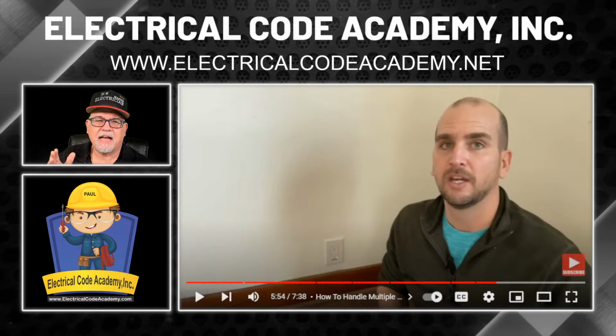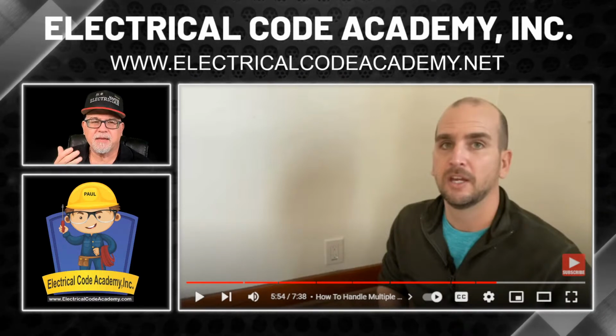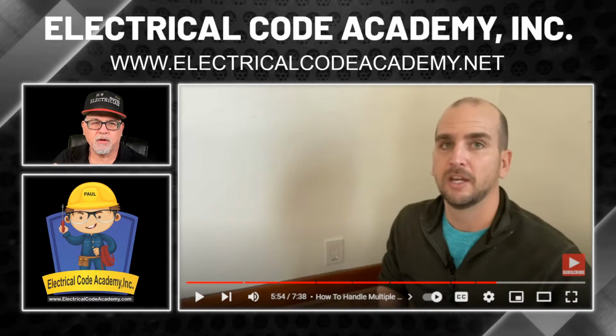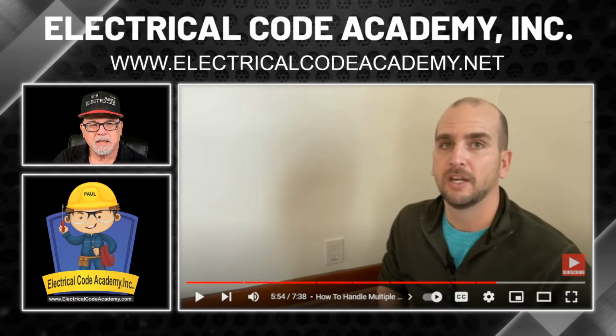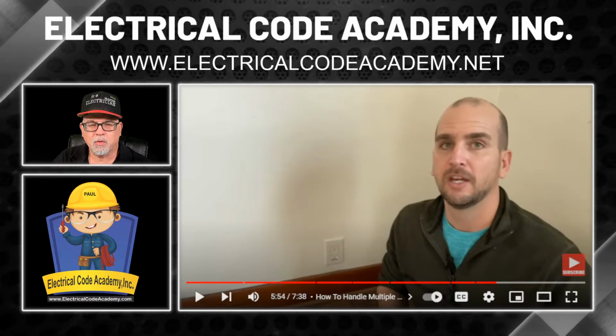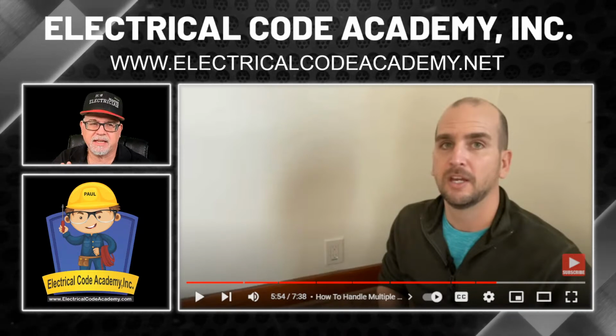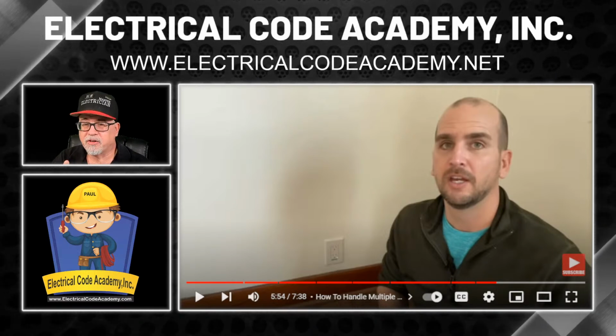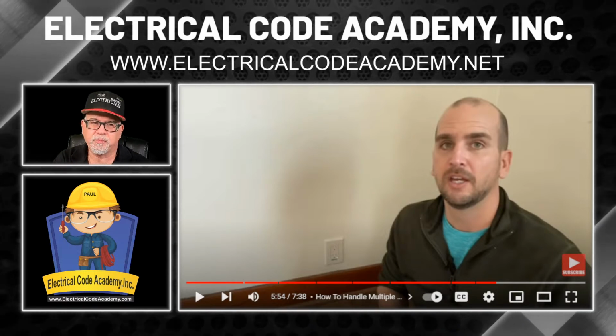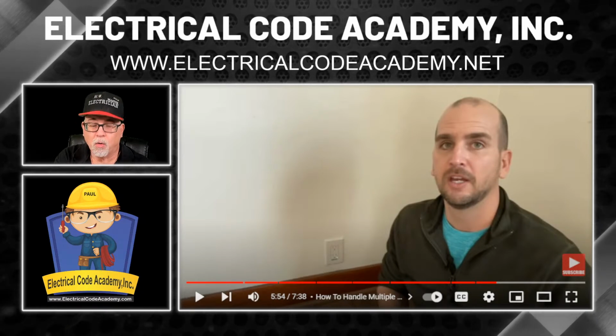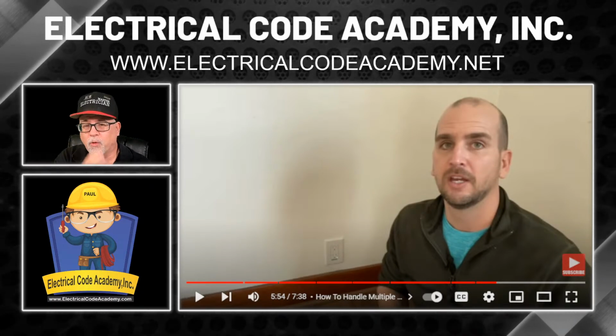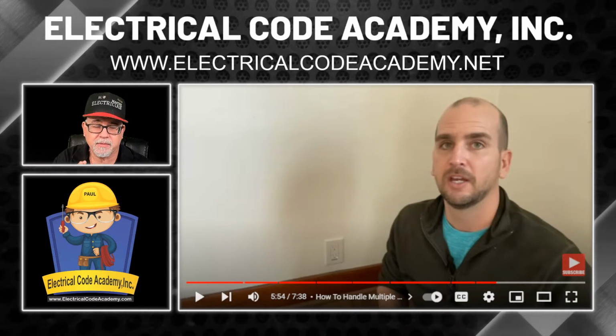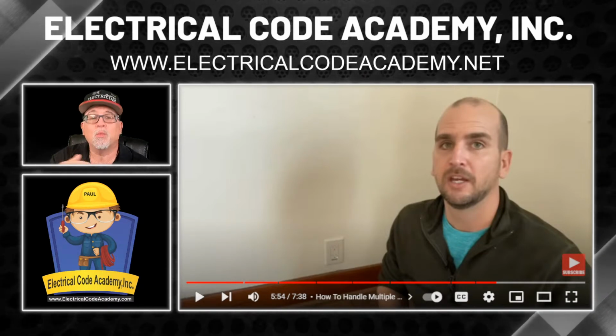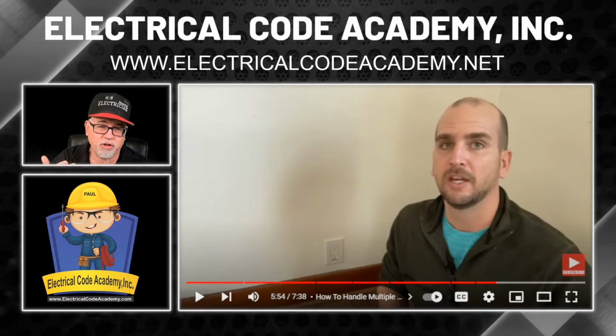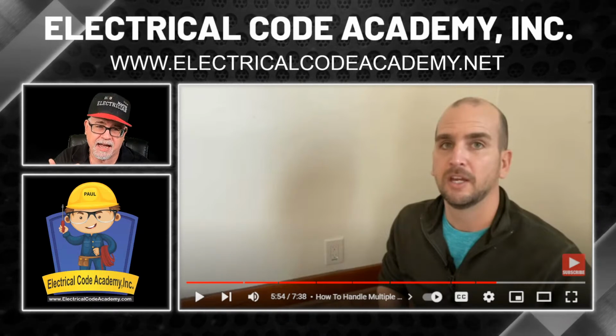So GFCIs work because it's looking for the imbalance of the draw of the current between the hot and the neutral. Typically, GFCIs work on what we call a 5 milliamp nominal, but the standard calls for it to be 4 milliamps or less, or 6 milliamps or greater. So at 4 milliamps or less, it will not trip. At 6 milliamps or greater, it will trip. So that is leakage current, not traveling back on its intended path.